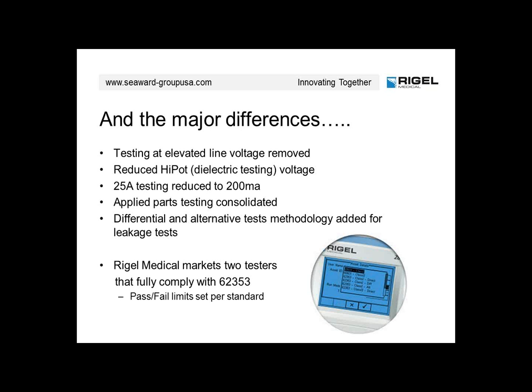25 amp testing is reduced to 200 milliamps. Applied parts testing is all consolidated. So 601 had you test each individual applied part, each patient connection individually, and then also test lead to lead. In 353, those are all tied together. Like connections are all tied together. And then differential and alternative tests have also been added to the specification for leakage.